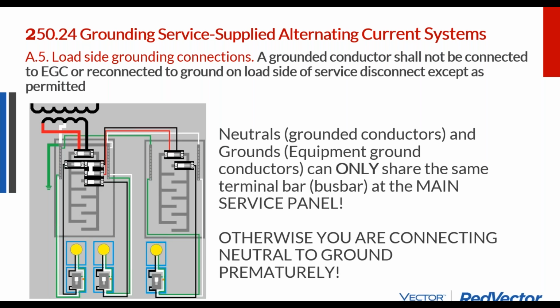If you just said, oh, my neutral's connected to ground, and so anywhere in the system I can connect my neutral to ground, we would miss the difference between the current that's faulting to ground and the current that's being consumed. We wouldn't be able to measure that in any known way. And so the danger is when you're designing these systems, code will tell you you need to make a main bonding jumper. You need to connect the neutral to ground. And the danger is you need to stop and say, okay, well, on this electric service that I'm adding to, there is already somewhere on site a neutral to ground connection. And so if I'm joining up to an existing electric service, I do not want to create a new neutral to ground connection. I'm going to use the one that's already been made as my one neutral to ground connection.